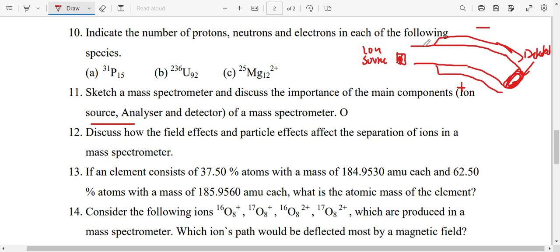And then at some point in the middle here, we are going to have the accelerator, which accelerates ions. We are going to have something like this, where ions are going to be accelerated in that region. We also have a vaporizer at the beginning; those are some of the parts. Now I want something very simple for us to discuss, where we just show the analyzer and also the detector. So we've already seen the detector from here. What is the function of the analyzer and what is the function of the detector? Let me just get the analyzer from here.